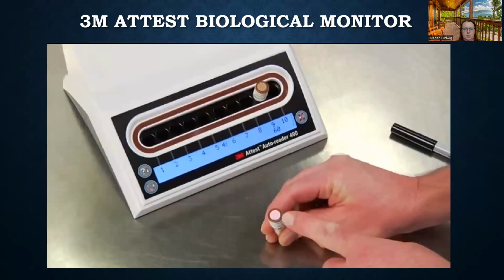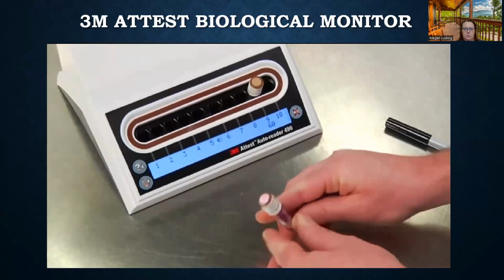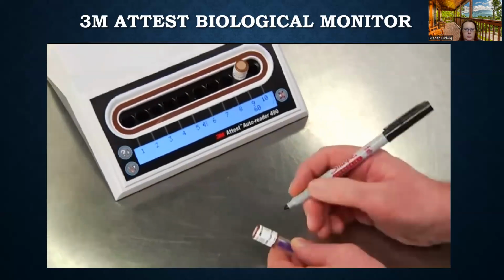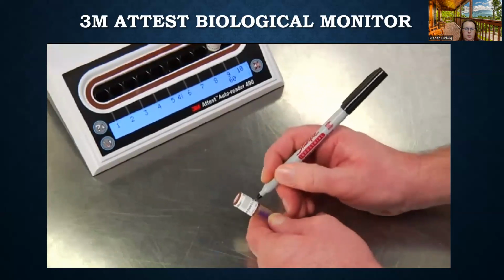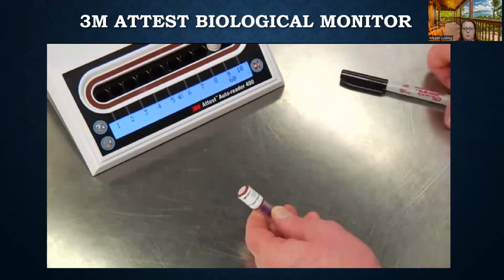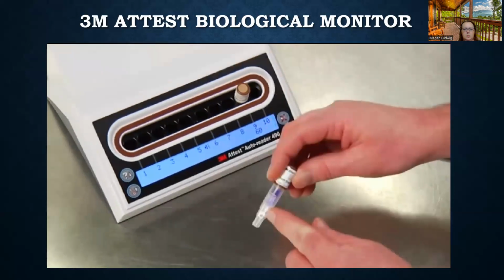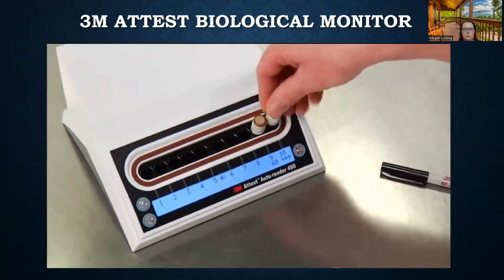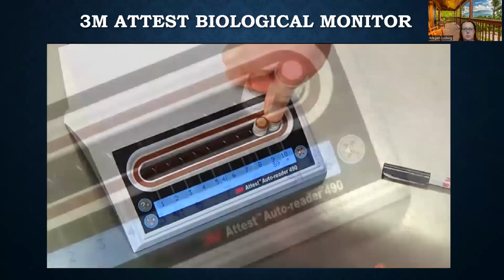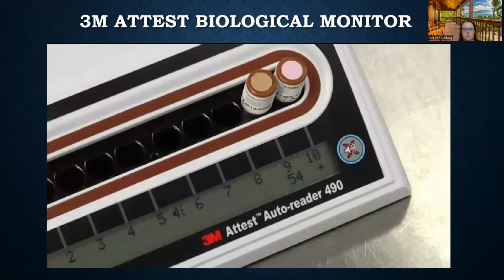Each day that a processed 1492 VBI is incubated, activate and incubate an unprocessed 1492 VBI as a positive control. The positive control should be from the same lot code as the processed biological indicator. The positive control BI should provide a positive fluorescent result.